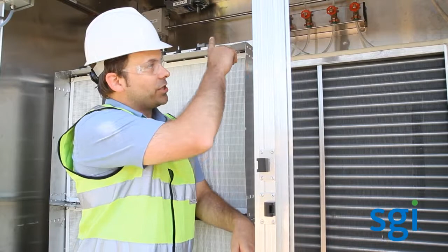The servers' heated air, we bring that back over the top for cold climates, and also to be able to keep this area at a certain temperature as well as to keep the servers at a certain temperature. But by adding the DX coil and/or the chilled water coil, it offers the customer the ability to have supplemental cooling and/or emergency cooling. That's an option. It's completely designed to be running, as we mentioned, fully on outside air and recirculation as we talked about. But the option is here for those kinds of customers.